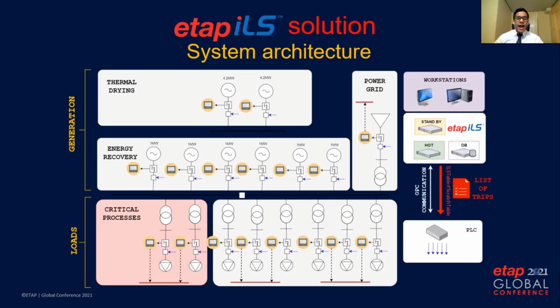On the other hand, the ILS server performs the logical processing of the data to predict the behavior of the system in case of loss of any of the available energy sources. A trip command list is loaded to the master PLC continuously. The PLC waits for a power loss event. When an event happens, the PLC immediately operates on the load breakers selected by ILS to remove what is necessary to maintain system stability. The ILS server has a redundancy server, which can act as an emergency or maintenance backup for the main processing server.